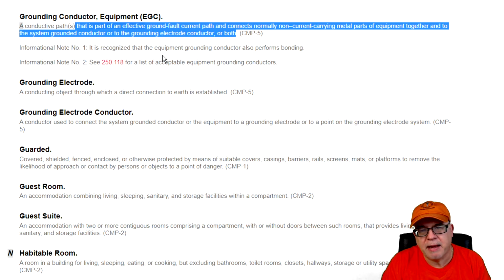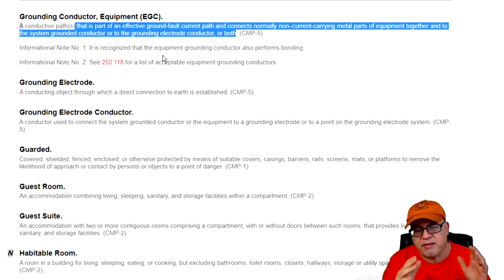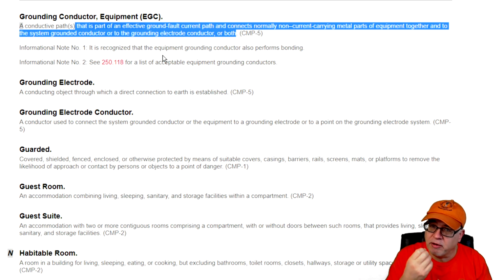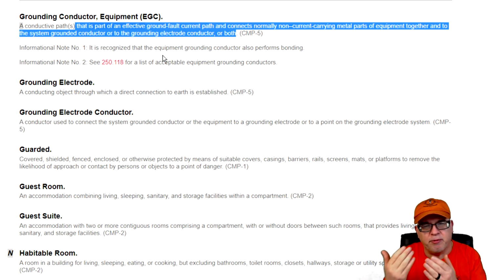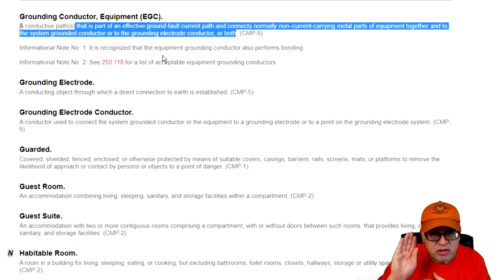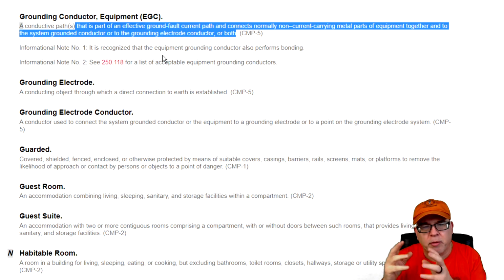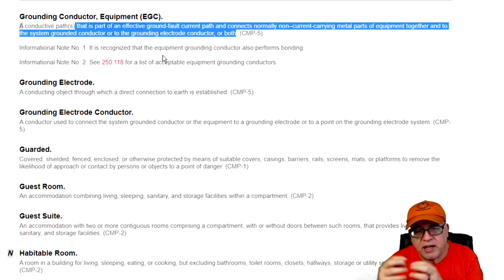So, in this application, typically the EGC is going to run with the branch circuit out. If you've got a feeder to that panel from the service, on the load side of that service, then that's a feeder, as we talked about earlier. It's going to have a separate grounded neutral conductor in there, and it's going to have a separate equipment grounding conductor in there so that we can float the neutral, basically not making contact with the enclosure downstream. But that equipment grounding bus does make connection to the metal, and that's where you're going to bring all your equipment grounding conductors, to a common location.